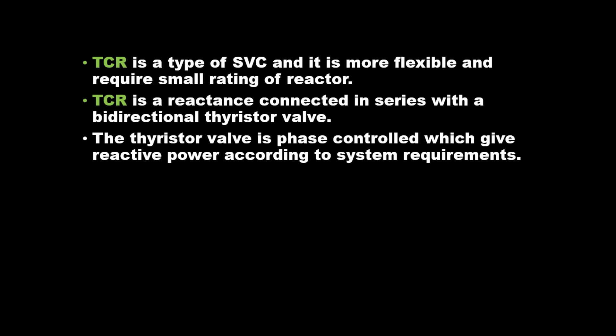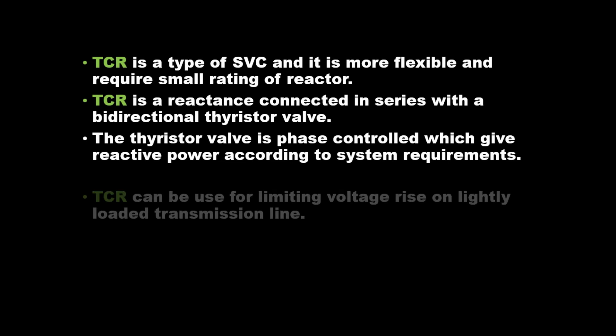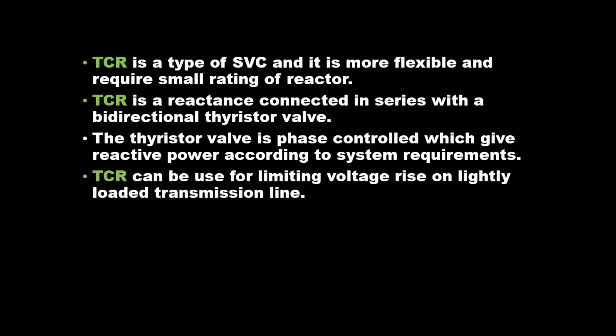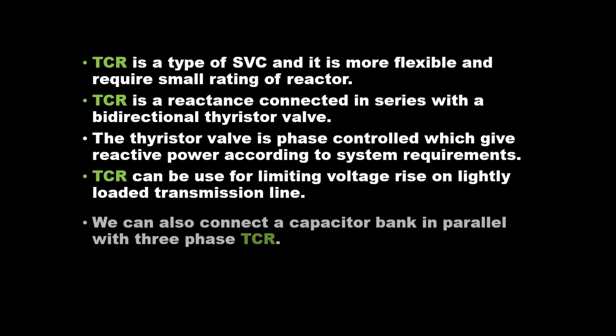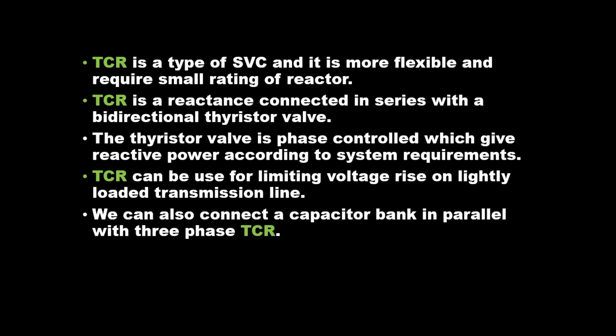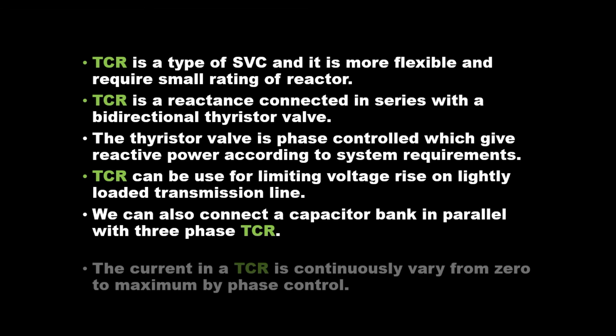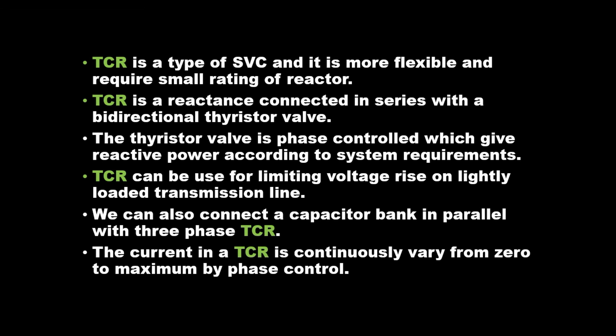TCR can be used for limiting voltage rise on lightly loaded transmission lines. We can also connect a capacitor bank in parallel with a three-phase TCR. The current in a TCR continuously varies from zero to maximum by phase control.